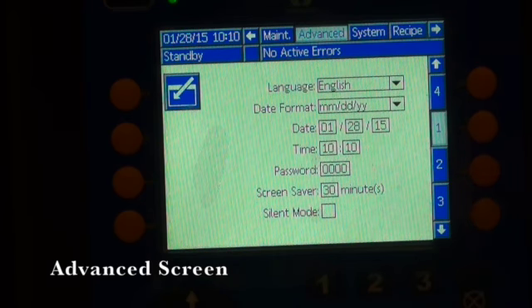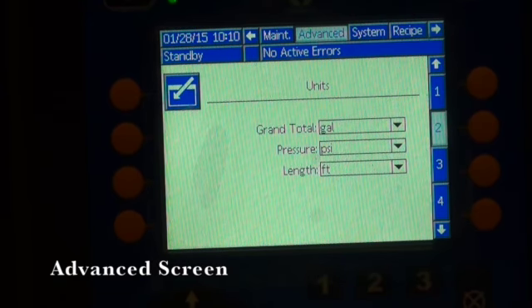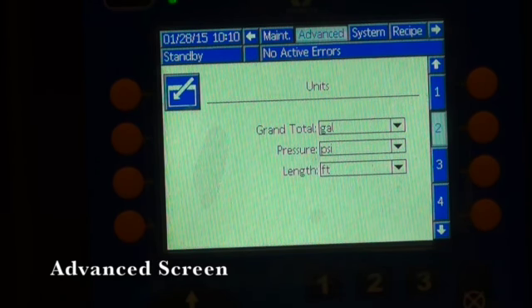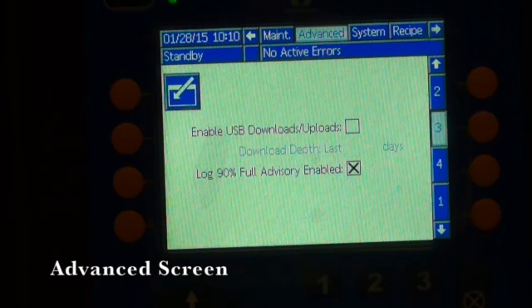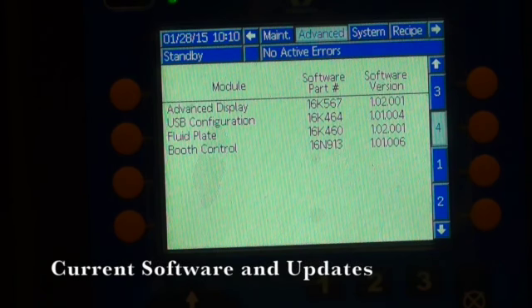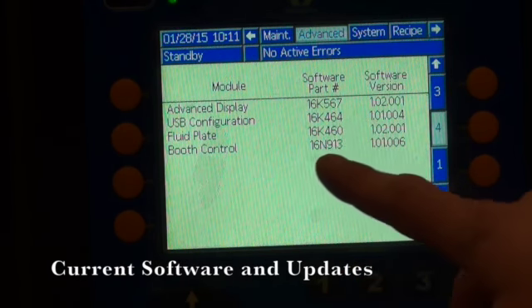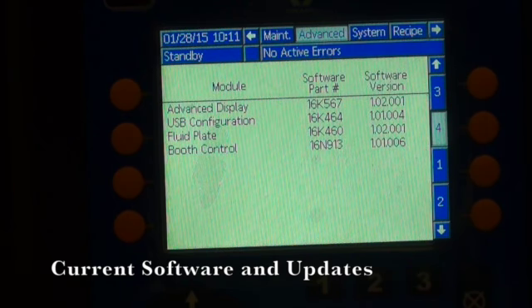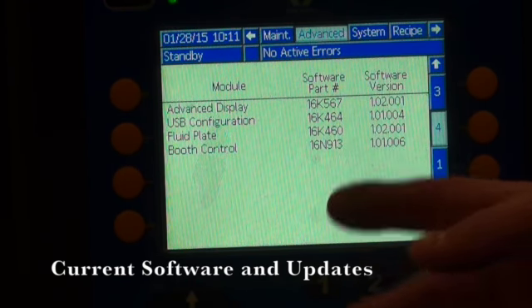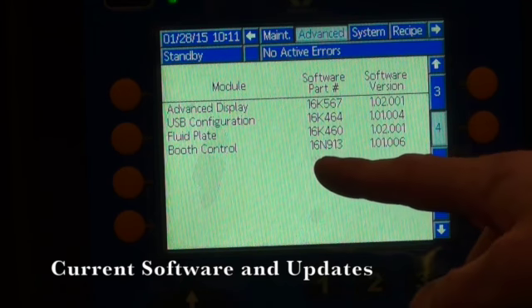The next screen over is what they call the advanced screen. This is pretty much just the language you want, date, time, when you want your screen saver to kick in. It's going to give you how you want it read. You want it read in gallons, you want your pressure in PSI, you want your hose length in inches or feet. And this is also where you would program in that you want it hooked up to a computer. And then last but not least on that screen, it's going to give you what software is currently loaded in this machine. If there's software updates, it'll show up here that your software number or software version is behind.